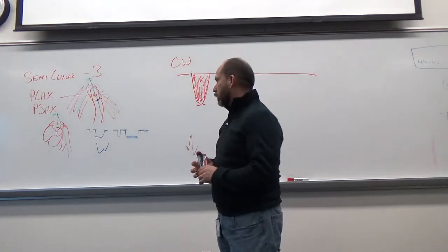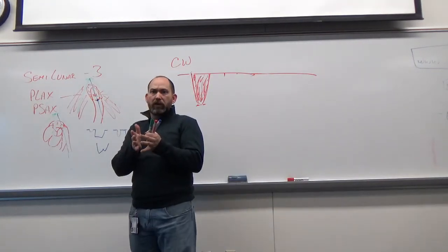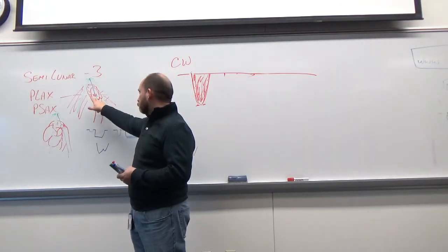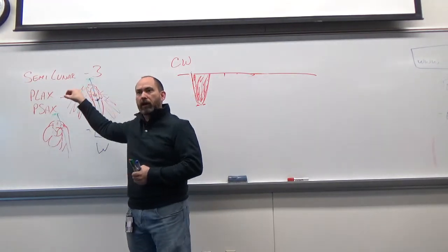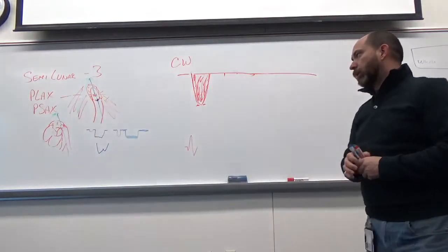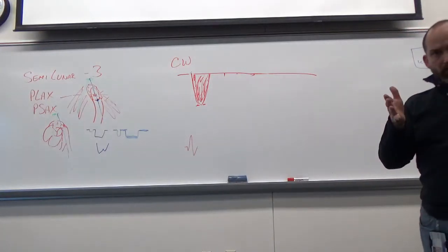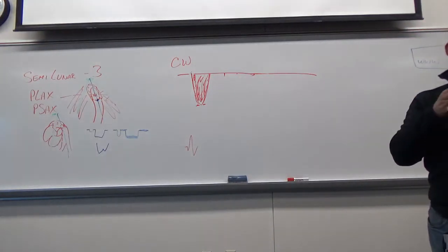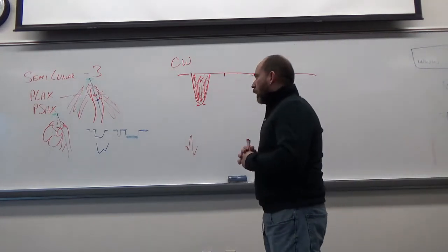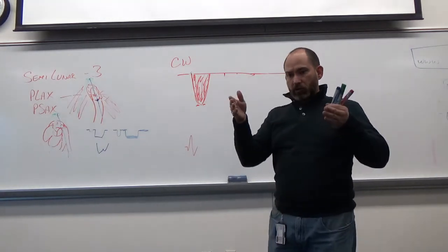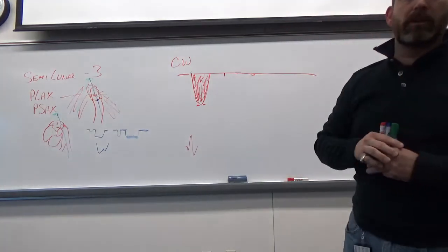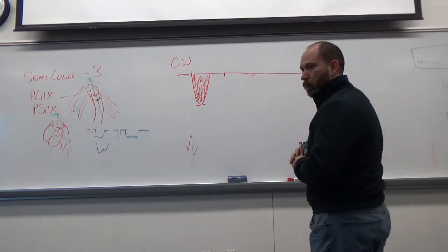Generally speaking, from an engineering standpoint, CW doesn't really need it, because it's not range specific, but the way that modern transducers work, they do recommend that you put that dot at about the area that you're interested in, even though it's not technically required. The beams are coming from a big crystal, not like the old pencil probes, where it's just a single crystal with no focus, they just shoot. One fires, one reads, but in these they're using different crystals to fire and read depending on where that point is. So it's not range specific, but it's recommended you put that on your area of interest.